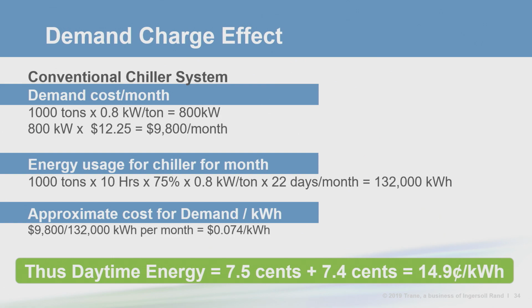At peak, when it's running its air conditioning at full load, this 1,000-ton unit, at an efficiency of 0.8 kW per ton, including the pumps and cooling tower, the chiller plant would add 800 kW to the summer kW demand. At $12.25 per kW, this would add $9,800 to the monthly cost. That $9,800 is the numerator. Remember, we are trying to go from dollars to cents per kWh.